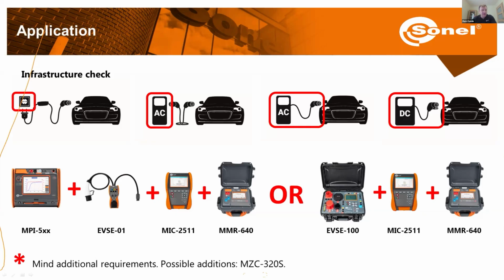Okay, now here I put asterisks. In case our charging station is very close to a transformer, then fault loop impedance may have very small values, so we will need to use a more precise meter. But that's in very particular cases. So here we have high current fault loop impedance meters of the MZC series, at least the 310 or 320, or some higher models.